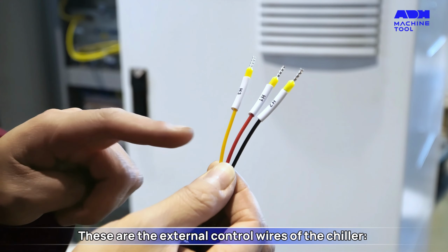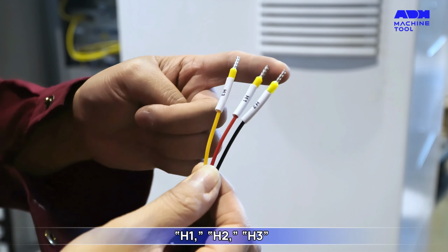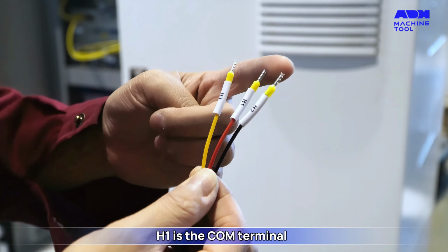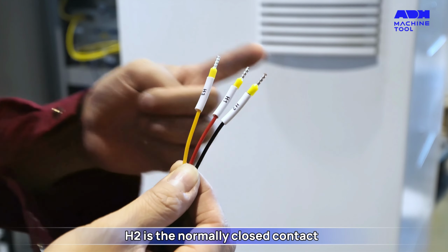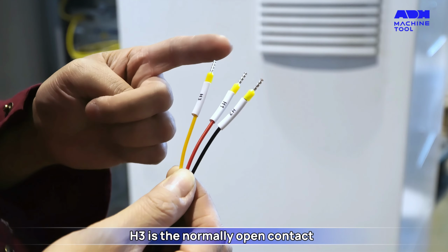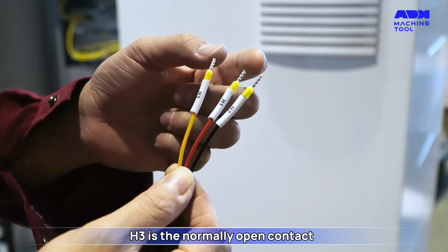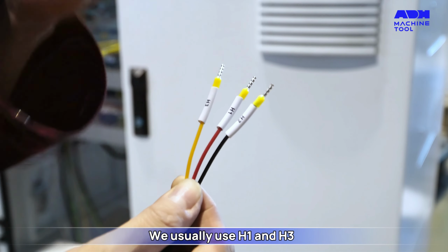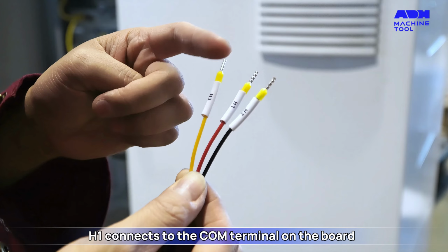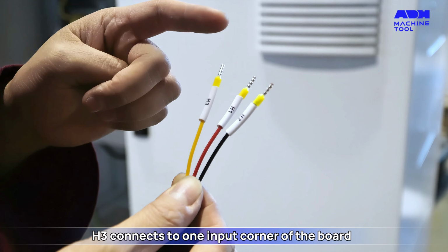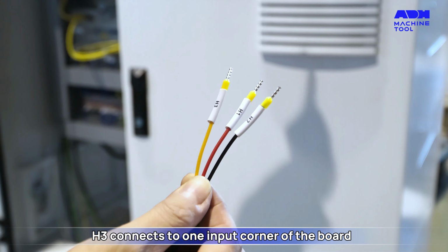These are the external control wires of the chiller. H1, H2, H3. H1 is the COM terminal. H2 is the normally closed contact. H3 is the normally open contact. We usually use H1 and H3. H1 connects to the COM terminal on the board. H3 connects to one input corner of the board.